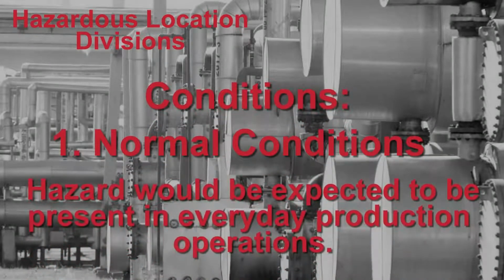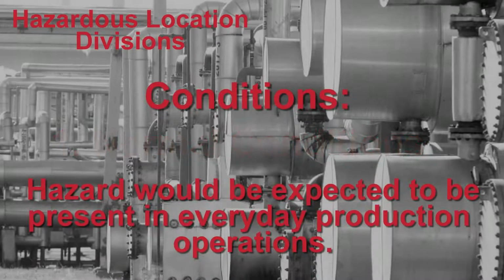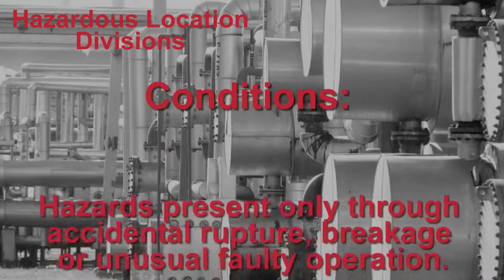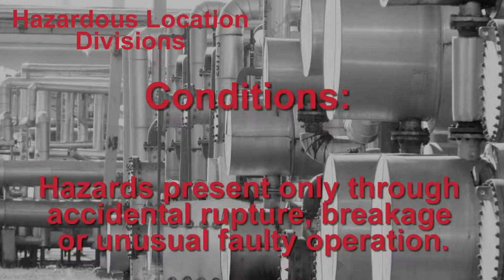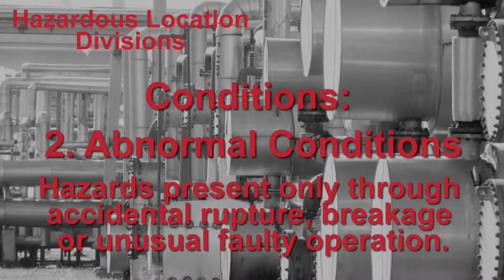In the normal condition, the hazard would be expected to be present in everyday production operations. When the hazardous material is expected to be confined within closed containers or closed systems and will be present only during accidental rupture, breakage, or unusual faulty operation, the situation could be called abnormal.